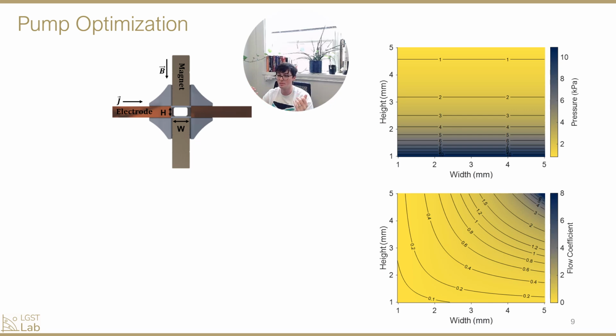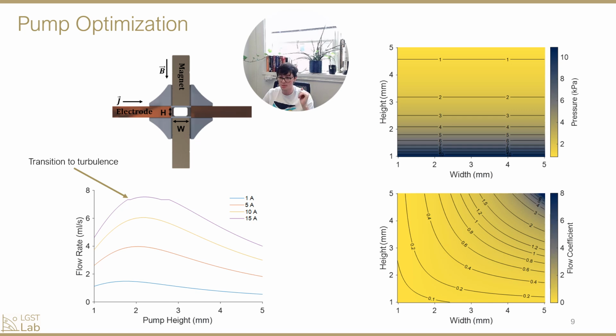So how do we balance these two things? The flow coefficient says we want a large height, the pressure says we want a small height. Where do we lie? What's the optimal height? It turns out that depends on what else is in your system — how many pumps you have, how much current you're putting in, a variety of factors. So we have just one sample use case here.